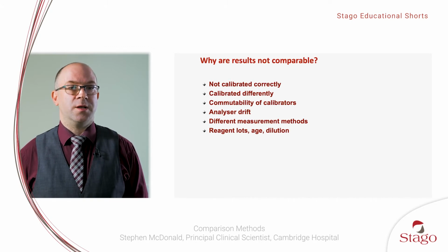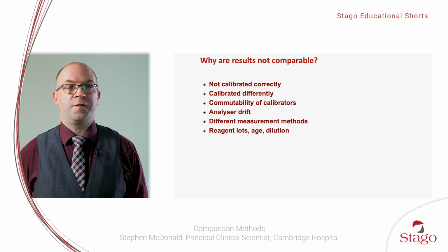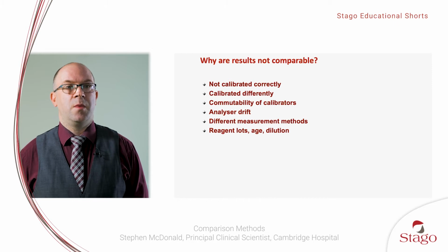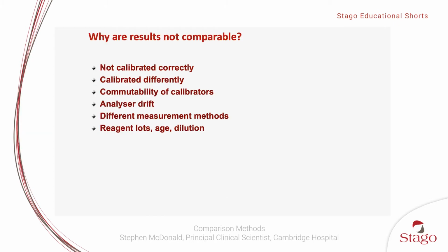Even if we do comply to that and they are calibrated correctly, we can have problems with drift over time as well. Calibrations have a finite lifetime. We have to have a regular calibration schedule to make sure that the calibrations are stable over time. And of course we do measure different measurements across different measurement methods as well. So one technique might give a result for the same measurand that is compared to another technique which might be slightly different.